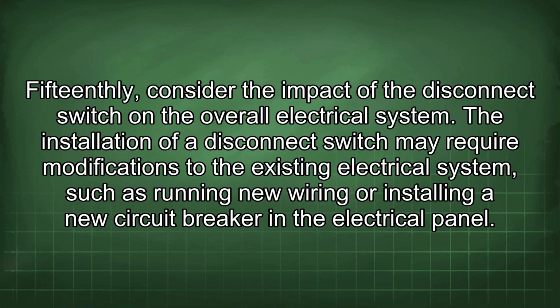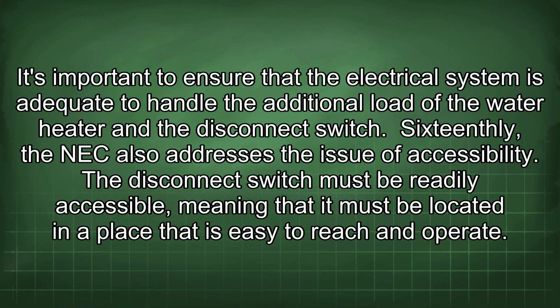15thly, consider the impact of the disconnect switch on the overall electrical system. The installation of a disconnect switch may require modifications to the existing electrical system, such as running new wiring or installing a new circuit breaker in the electrical panel. It's important to ensure that the electrical system is adequate to handle the additional load of the water heater and the disconnect switch. 16thly, the NEC also addresses the issue of accessibility.